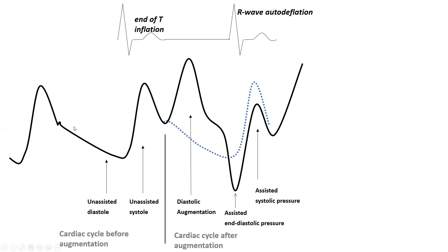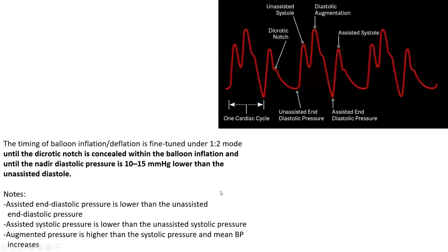This is another illustration of how the pressure would look if we did not augment in this patient. The diastolic pressure is actually lower after augmentation, and the systolic pressure is lower after augmentation. This is because that's the purpose of the balloon pump. It creates that deflation and sucking motion that creates a vacuum and dips the diastolic pressure and the systolic pressure. This is a manifestation of that massive reduction in afterload. You actually seek to have the diastolic pressure after augmentation lower than the diastolic pressure before, and the systolic pressure lower than before.